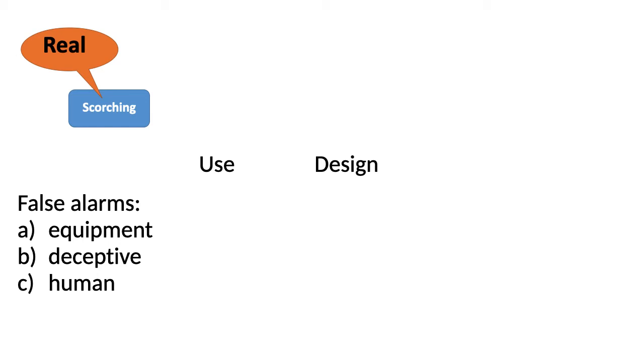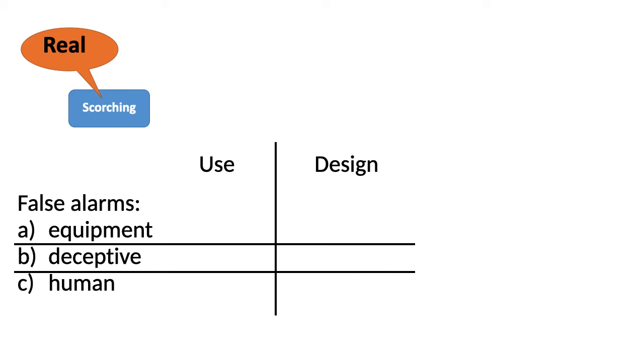However, if the same happens in a soldering workshop, so I have a soldering or a welding workshop, and the smoke detector is triggered, then actually the fire installation was not designed properly, because the person who designed and installed the fire installation should have known that soldering is happening in a soldering workshop, so he should have used a different design for the fire installation. And you can actually distinguish this for all three types of false alarms. Well, I won't go into details into these six subcategories.